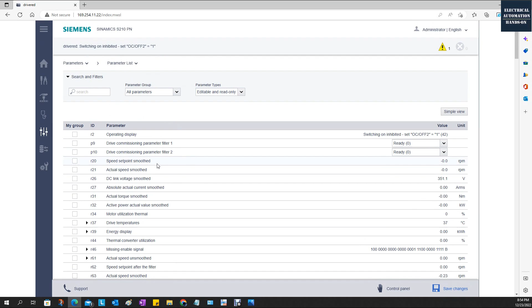And then let's go to the backup restore. This is very useful. At the end of the project, you definitely want to back up the drive parameters in case one day the drive fails or you change to a new controller. Then you can use the backup file to do the restore here. To back up this servo drive, I can click this backup parameters, and then click open file. You will see this zip file includes two files inside. You do not need to unzip it. You can rename it, for example, backup underscore this servo drive. So store this file somewhere.